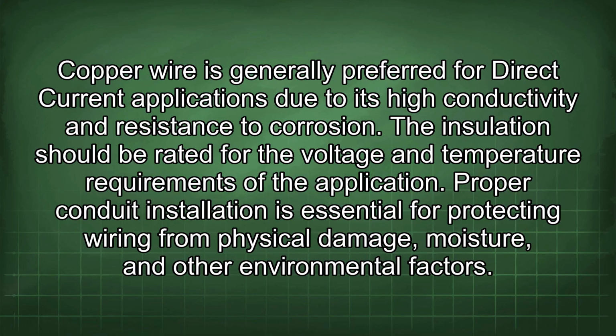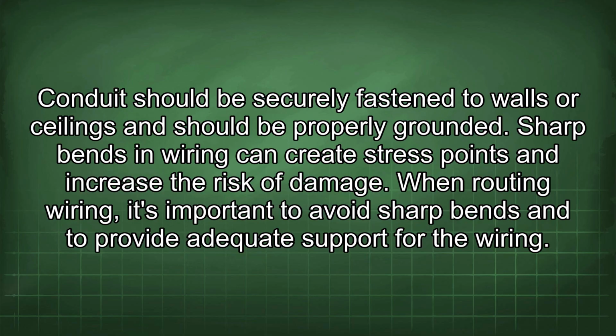Proper conduit installation is essential for protecting wiring from physical damage, moisture, and other environmental factors. Conduit should be securely fastened to walls or ceilings and should be properly grounded. Sharp bends in wiring can create stress points and increase the risk of damage. When routing wiring, it's important to avoid sharp bends and to provide adequate support for the wiring.